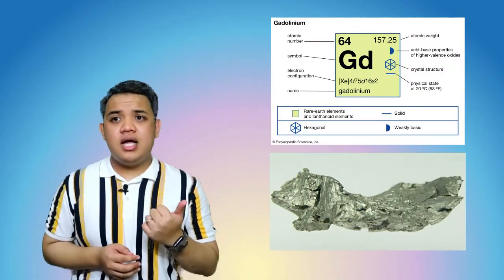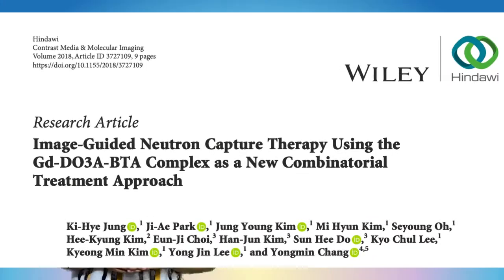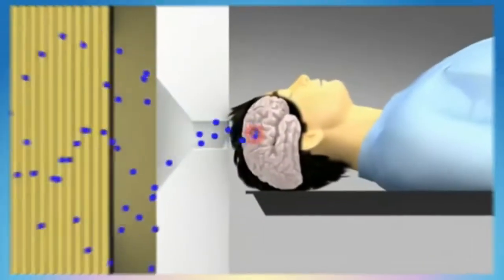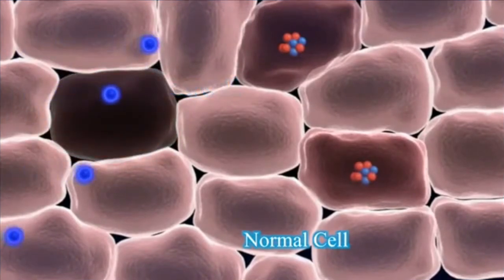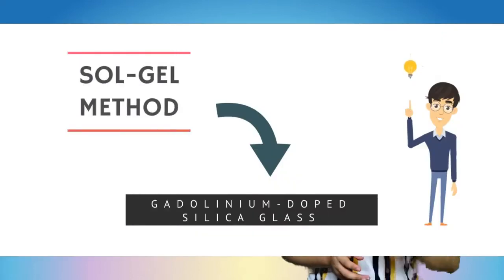As one of the rare earth materials, gadolinium (Gd) has properties that meet better medical neutron radiation dosimetry specifications, with a high thermal neutron cross-sectional absorption coefficient of about 254,000 barns. Building upon these reasons, a novel neutron radiation dosimeter is fabricated using a non-toxic sol-gel method based on the Gd-doped silica glass.